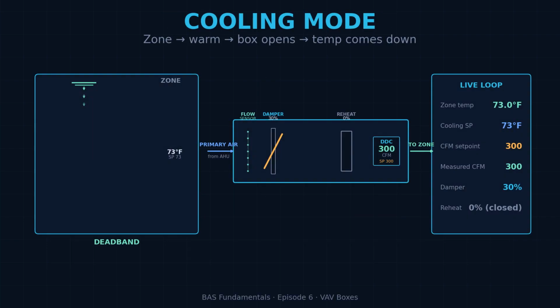Let's walk through cooling. Zone temperature climbs above the cooling set point. The outer loop output ramps up. CFM set point rises from the minimum cooling airflow, Vmin cooling, toward the maximum cooling airflow, Vmax cooling. The inner loop sees the new CFM target and drives the damper more open until the measured flow matches. Cold air pours into the zone. Zone temp starts coming down. The loops back off. All automatic, all smooth if the tuning is right.